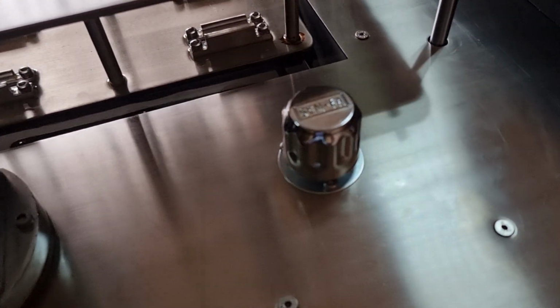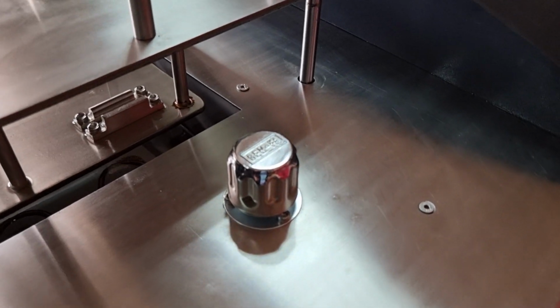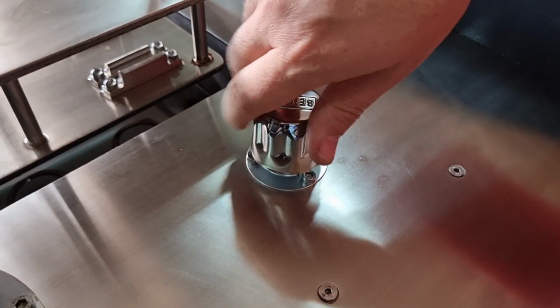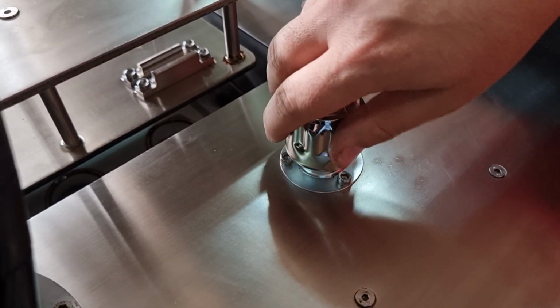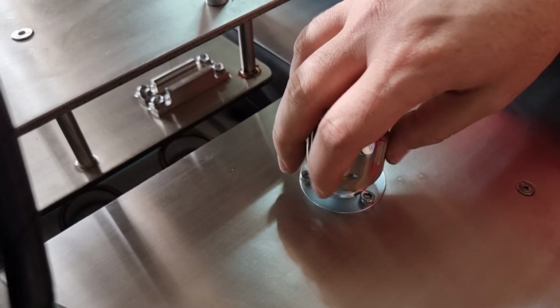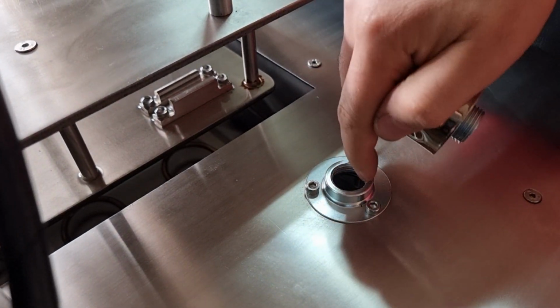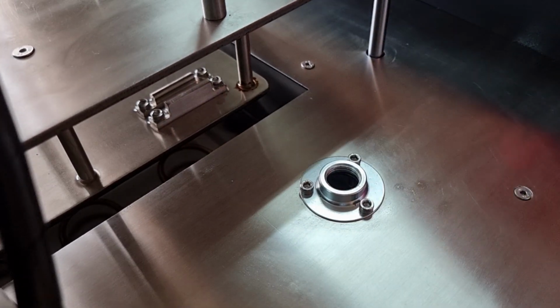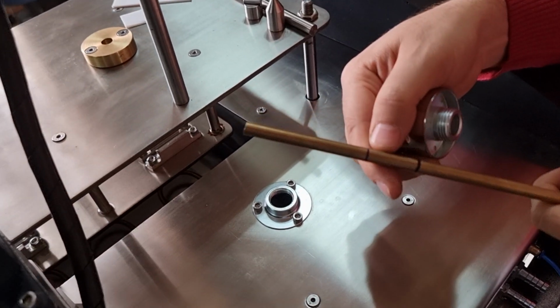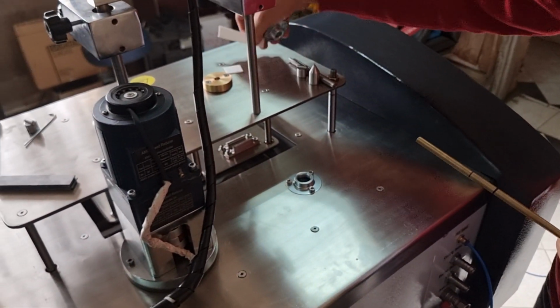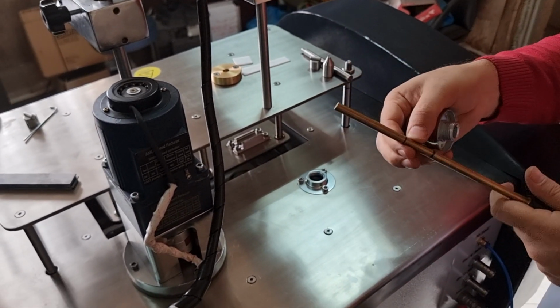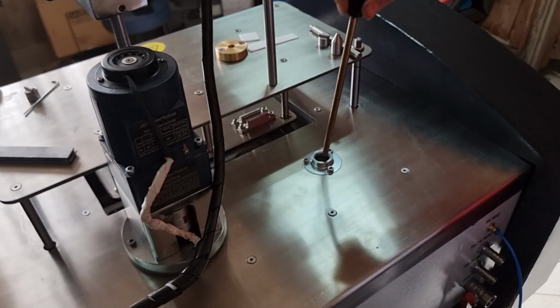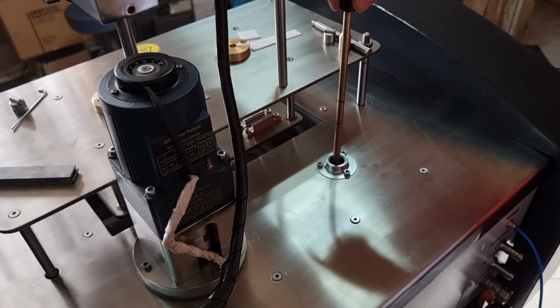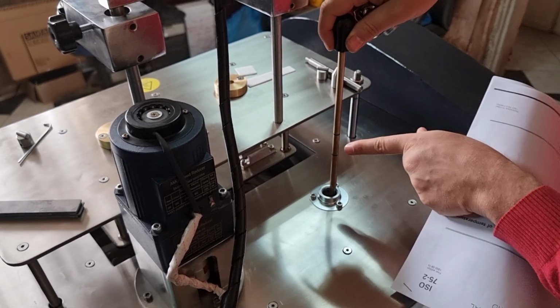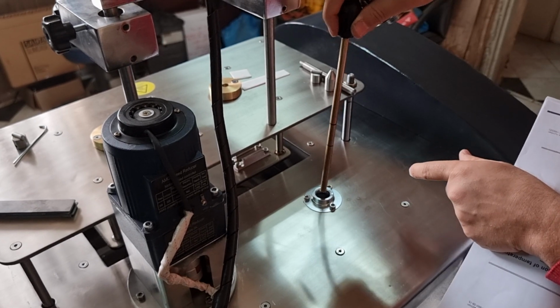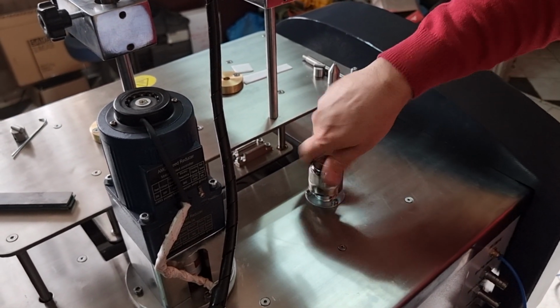For the start of the test, you need to fill the bath with silicone oil with the viscosity of 100. It is the most proper liquid for testing. You have a mark here. The minimum marking is enough for filling to cover the samples that you will put in the sample holder here. When you're filling, you need to check the level of the oil using this rod, and it should pass the minimum marking on this rod, and you can easily fill the oil of the bath.